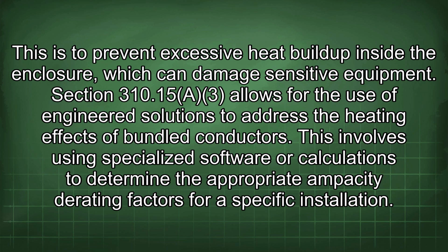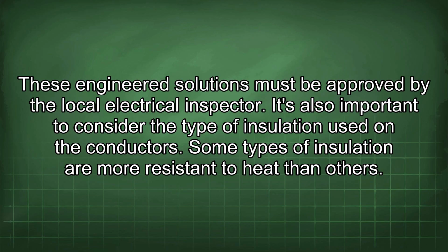Section 310.15(A)(3) allows for the use of engineered solutions to address the heating effects of bundled conductors. This involves using specialized software or calculations to determine the appropriate ampacity derating factors for a specific installation. These engineered solutions must be approved by the local electrical inspector.